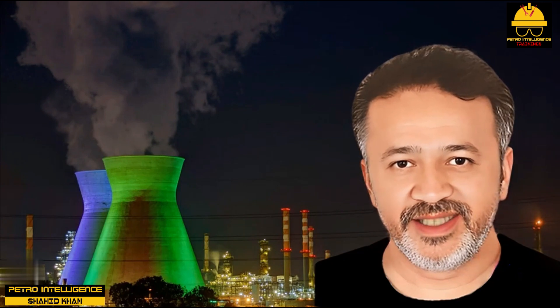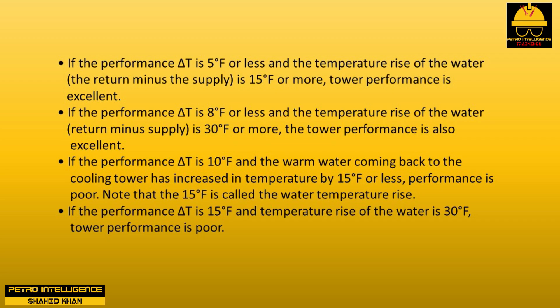Calculate the performance delta T: this is the difference between the water leaving the tower and the wet bulb temperature. Performance is excellent if the delta T is 5°F or less and the temperature rise of the water (return minus supply) is 15°F or more. Performance is also excellent if the delta T is 8°F or less and the temperature rise is 30°F or more. Performance is poor if the delta T is 10°F and the temperature rise is 15°F or less.